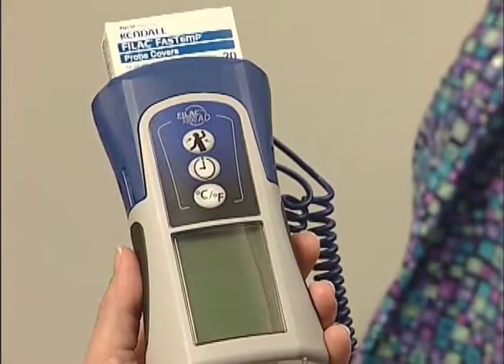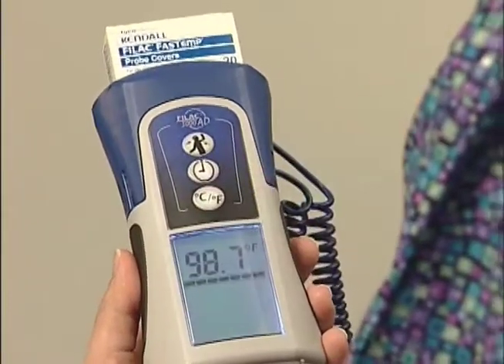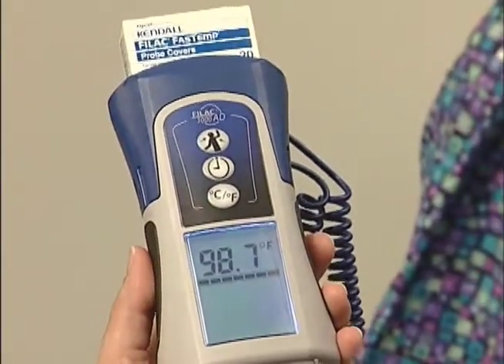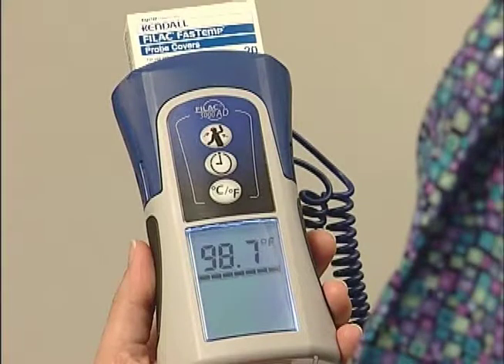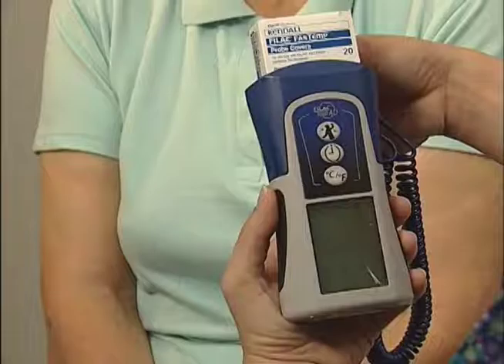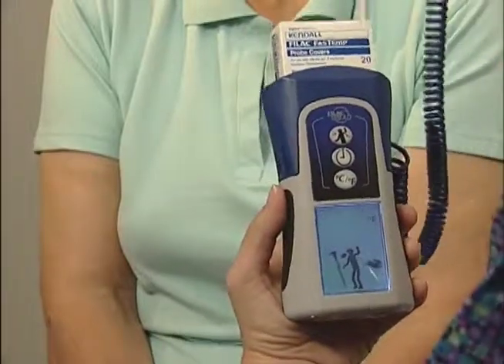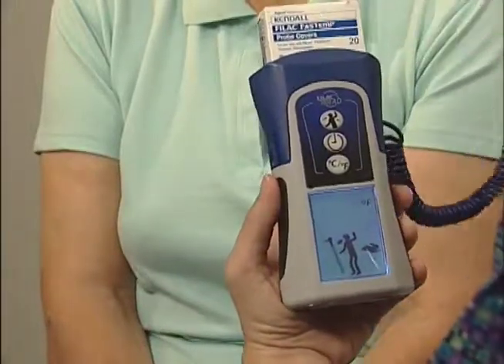You may view the most recent temperature reading by simply pressing the C degrees F degrees button on the front panel. The probe must be in the chamber and not have been removed since the last temperature was taken to display the reading. Withdrawing the probe from the chamber will erase the last temperature taken from memory.